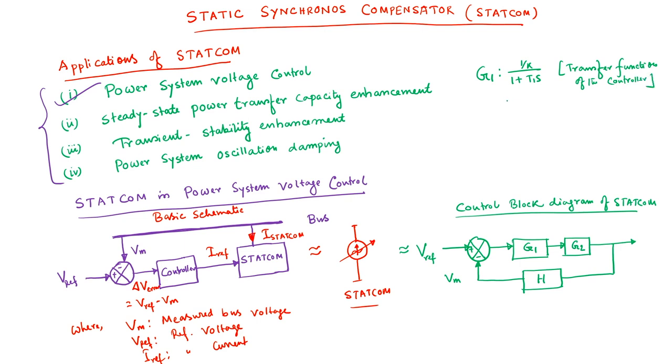And this k is the control characteristic slope. You know that similar to the SVC, we will also maintain a very small amount of positive slope, typically 1 to 5% in case of STATCOM also, to facilitate the parallel operation of the STATCOM, or the reactive power compensation sharing among multiple STATCOMs, and also for various reasons which I already discussed in case of SVC.